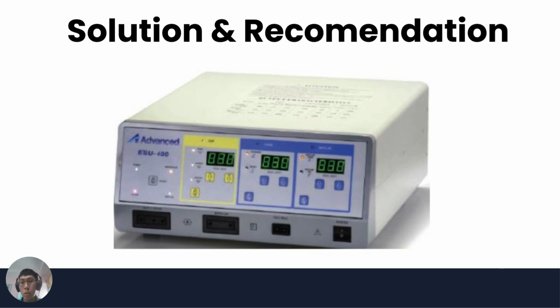and between 1200 and 4600 peak volts for spray coagulation. Bipolar coagulation mode should operate at a maximum of 100 watts and 200 peak volts. The unit should include a REM, independent output and visual and audible activation indicators, following the AAMI and IEC 60601-2-2 standard. It should also feature a power setting display and utilize a convection or fan cooling system. Lastly, the unit must have an alarm capable of producing volumes higher than 45 decibels at 1 meter.